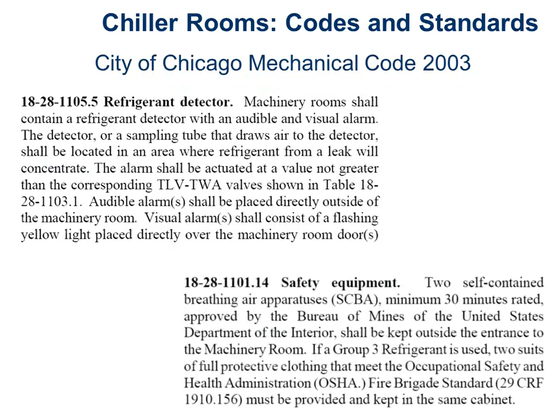If you look at the City of Chicago code, which a lot of you guys do projects in, there are very similar rules. I have to have visual and audible alarms both inside the room for people that are working in there and outside every single entrance to the room. Additionally, in Chicago, you have to provide scuba gear, right? So that's basically the face mask and tank. That way somebody can go in there and help rescue somebody else. In Chicago, you're required to have 2 tanks ready for 30 minutes each. It's not for me to go in there and hang out and try to work on stuff in there. It's for me to put the tank on, go in there, rescue my buddy, drag him out, right, and then open up the doors, make sure the fans are on, and try to ventilate this space out, and then go work on this thing later on. All right, so those are my main rules. Both ASHRAE and City of Chicago pretty much say the same thing for the gas detection portion of it.